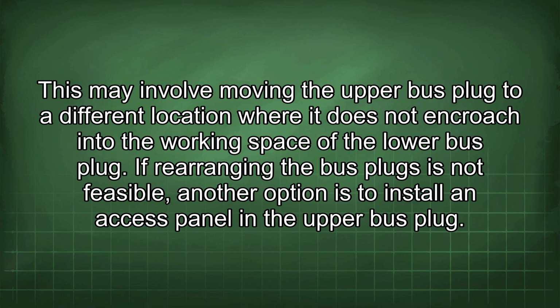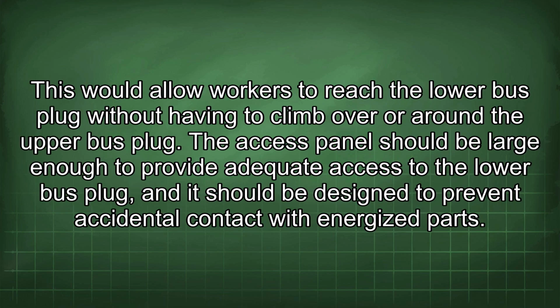If rearranging the bus plugs is not feasible, another option is to install an access panel in the upper bus plug. This would allow workers to reach the lower bus plug without having to climb over or around the upper bus plug. The access panel should be large enough to provide adequate access to the lower bus plug, and it should be designed to prevent accidental contact with energized parts.